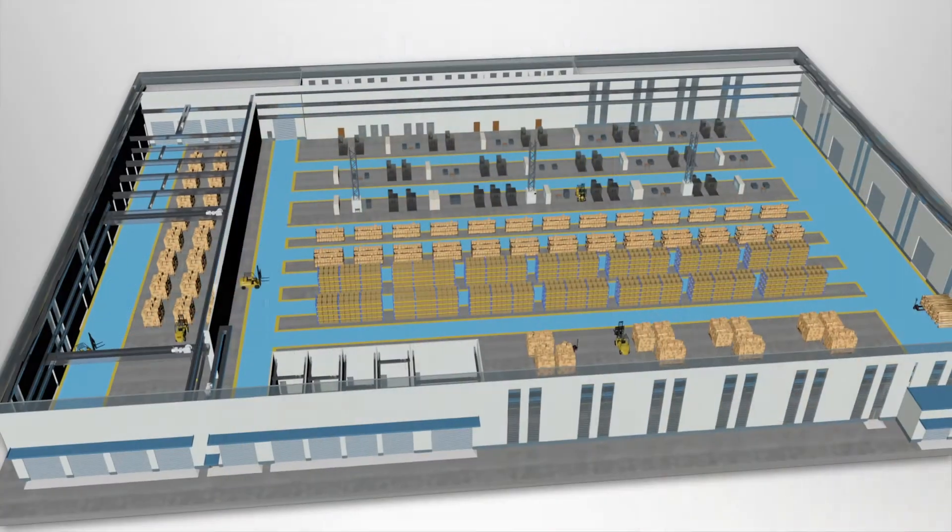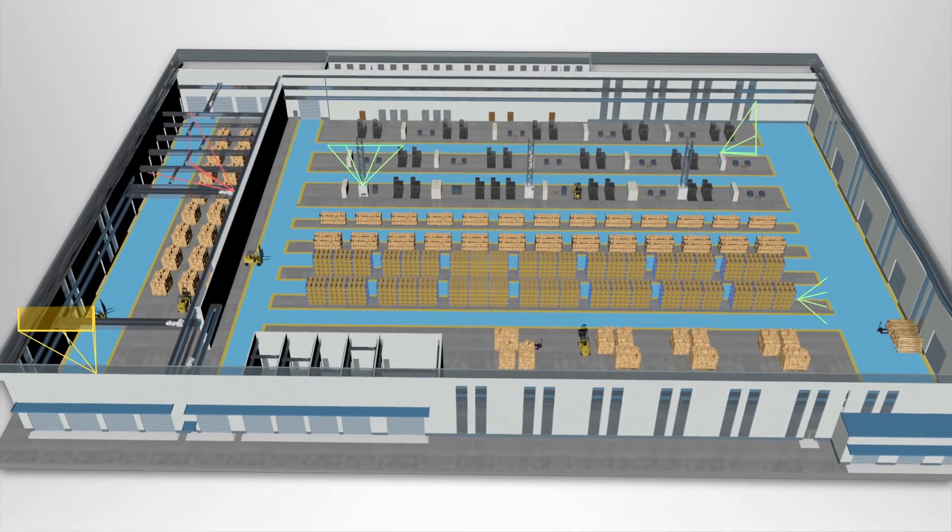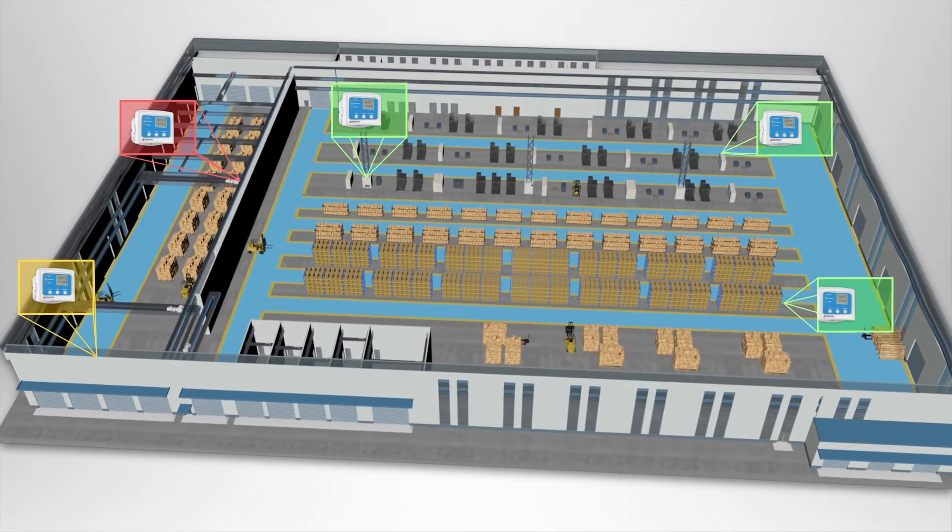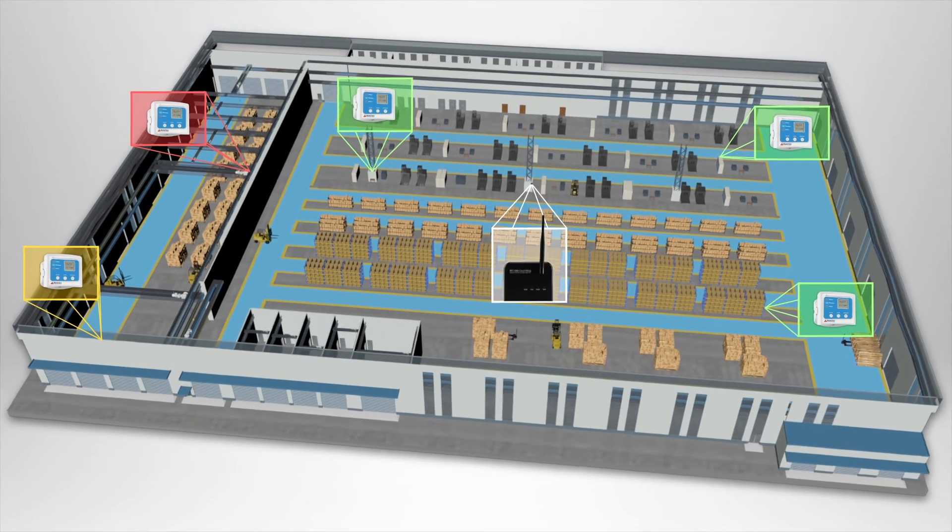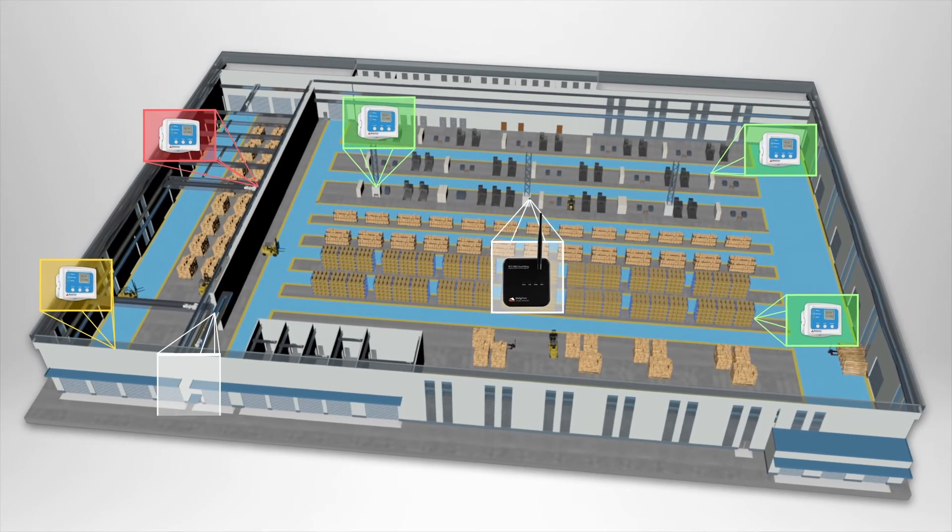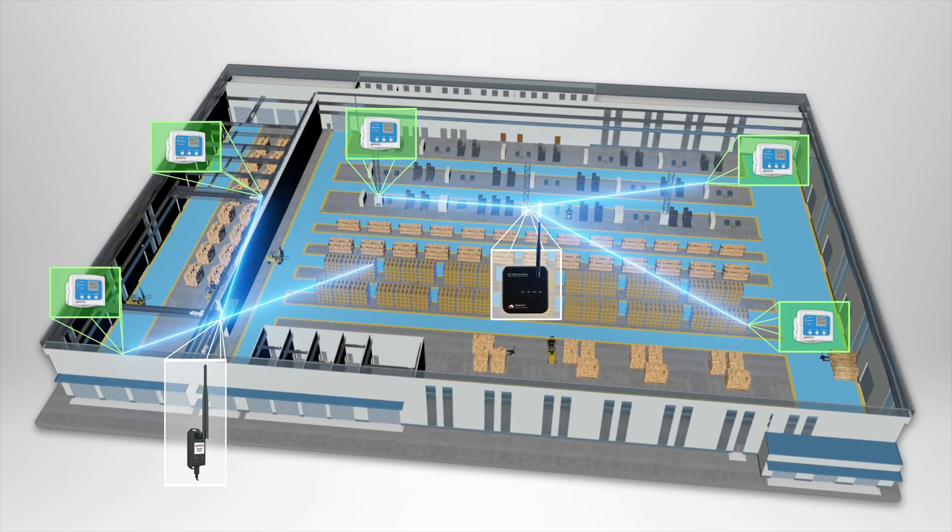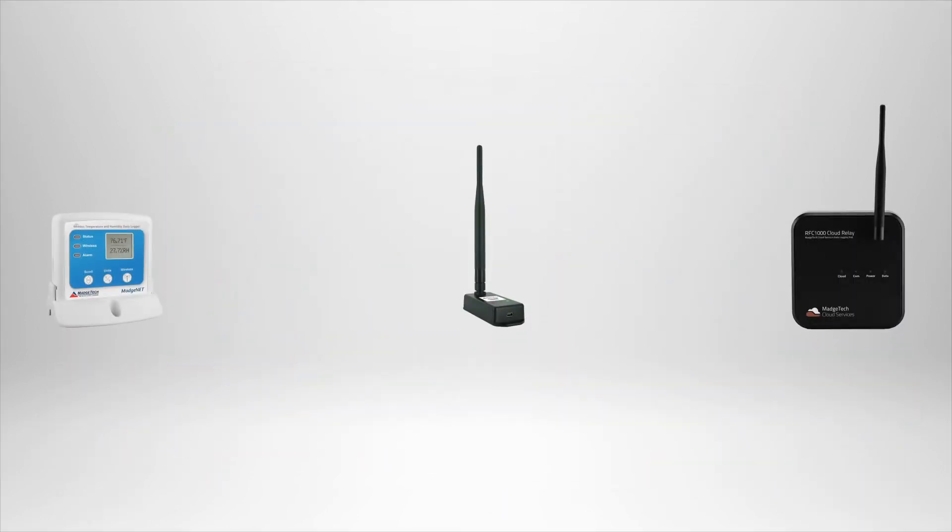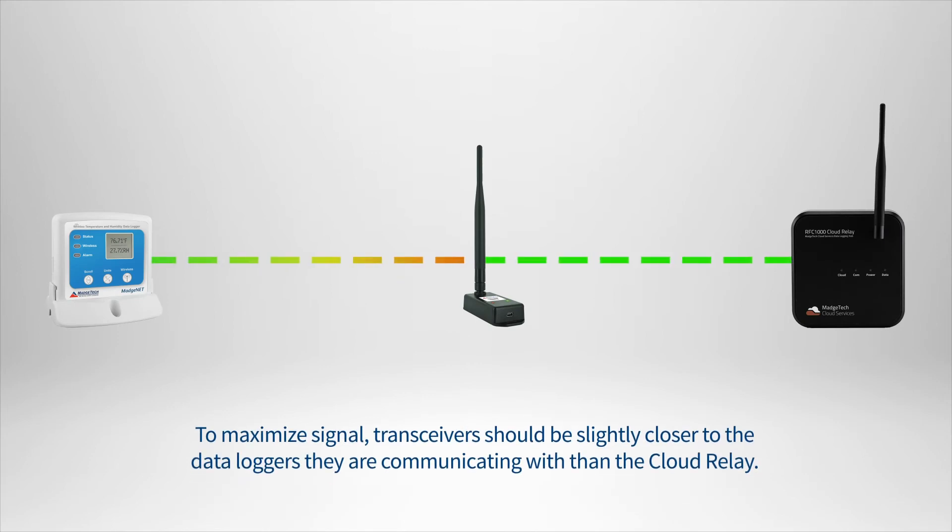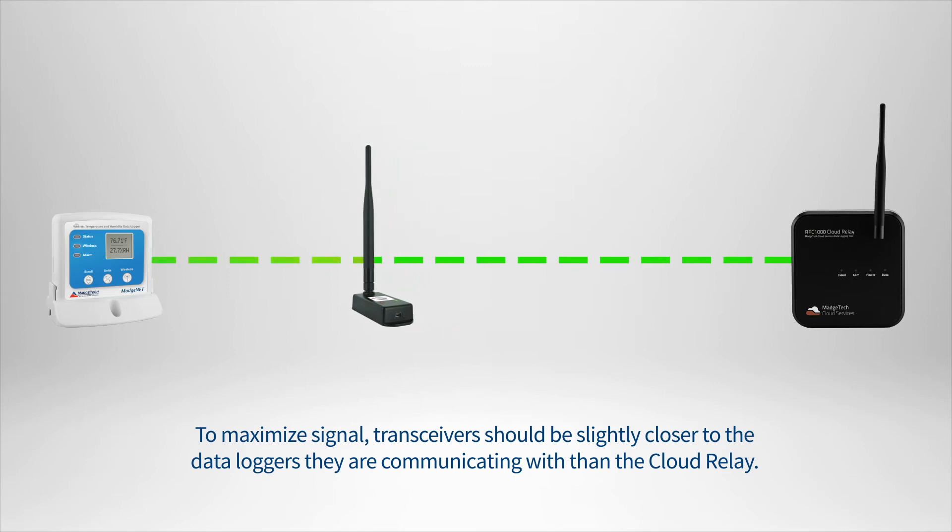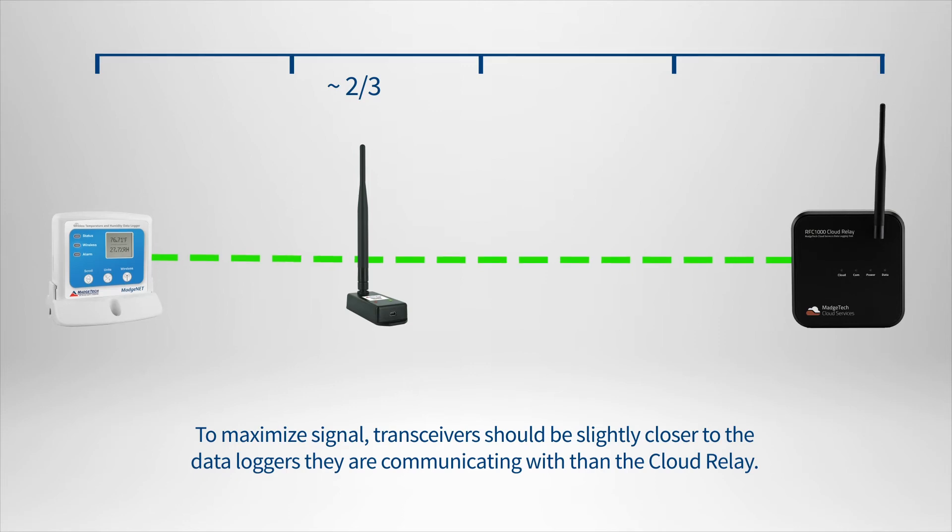With all these optimization tips in mind, physically locate the remaining data loggers with poor connection. One or more additional RFC-1000 repeaters can be deployed between the cloud relay and that logger to improve connection. It's important to note that RFC-1000s produce a stronger signal than that of data loggers, so the ideal placement won't necessarily be halfway, but instead closer to the logger, approximately two-thirds the distance between the device and the next closest repeater or cloud relay.